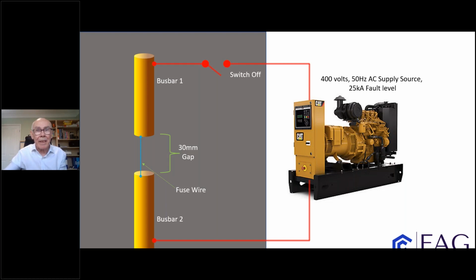In this diagram, you can see two copper bus bars separated by a 30mm gap and connected to a 400 volt electrical source with a respective short circuit capacity of 25,000 amps - the sort of output you get from a 1000 kVA transformer, which is pretty ubiquitous in industry. As you can see, there's no protective device in circuit, only a switch, and connecting the two bus bars is a piece of heavy gauge fuse wire, shown in blue.